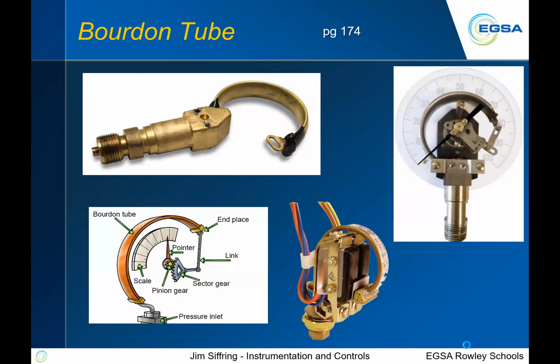So let's talk about Bourdon tube gauges. Bourdon tube is probably the most common pressure gauge you're going to find out in the world. And really all it is, is a brass or stainless steel or other type of material with a piece of tubing on the top. You'll see this piece of tubing on that upper left corner picture. Once you apply pressure to that fitting on the bottom of the device, that curved piece of tubing will want to straighten itself out. It's just the physics of it. We can take the end of that tubing and tie it onto a mechanical pointer, and it'll give us a visual representation of what's happening in that tube. As you increase pressure, the tube straightens out, moves the pointer, and we can calibrate that to read out in whatever type of pressure you want.